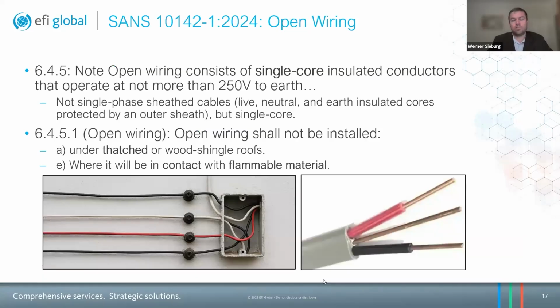The next clause that I've just decided to address, it's probably not as relevant, but perhaps in older buildings it might be. So 6.4.5 says that open wiring consists of single core insulated conductors that operate at no higher than 250 volts. So 250 volts, I believe that's just the normal standard distribution voltage. But so then on the left here, we've got once again an AI generated image of open wiring. Basically, this is a 3-wire plus earth, and basically the insulation of the conductor is only one layer. In other words, behind this red and white and black, there is the copper.